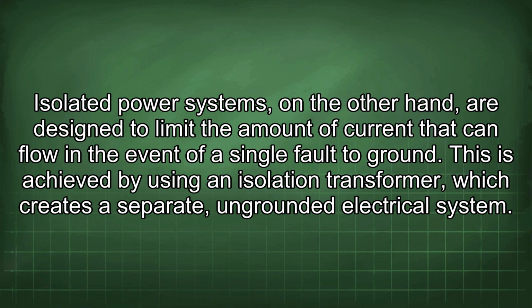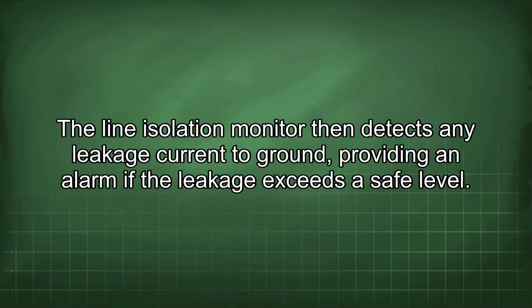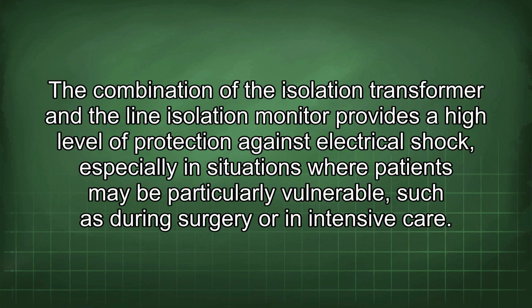This is achieved by using an isolation transformer, which creates a separate, ungrounded electrical system. The line isolation monitor then detects any leakage current to ground, providing an alarm if the leakage exceeds a safe level. The combination of the isolation transformer and the line isolation monitor provides a high level of protection against electrical shock, especially in situations where patients may be particularly vulnerable, such as during surgery or in intensive care.